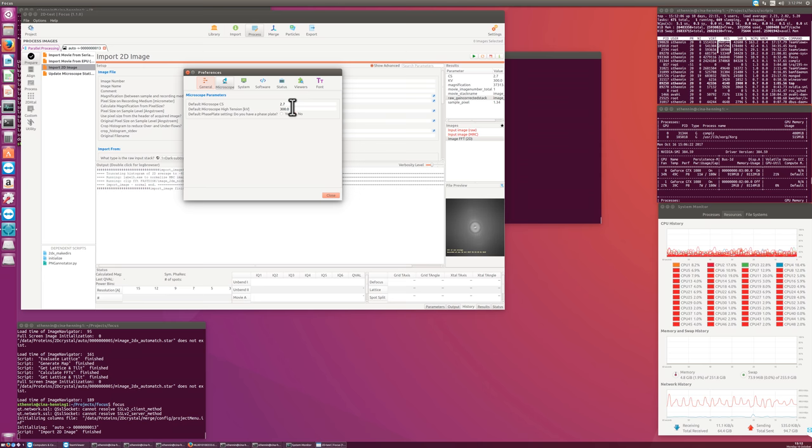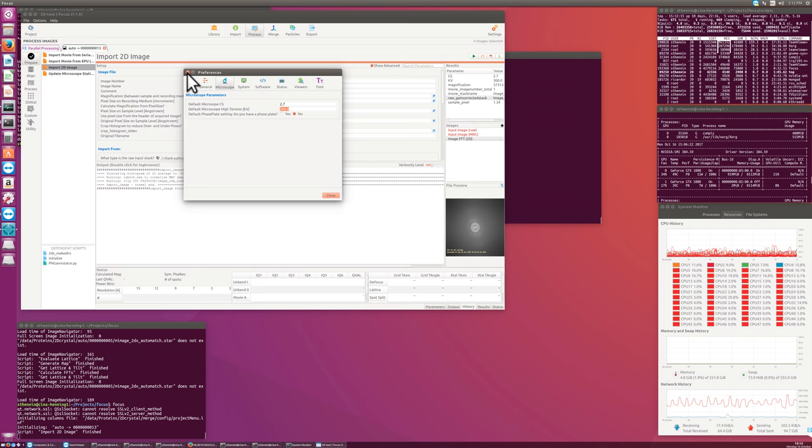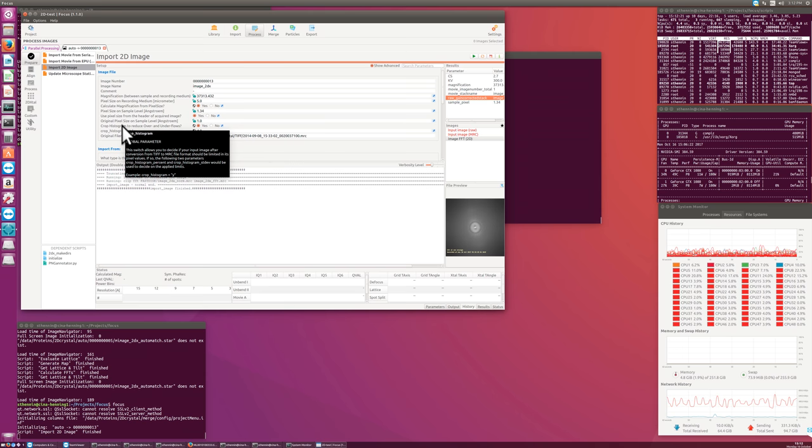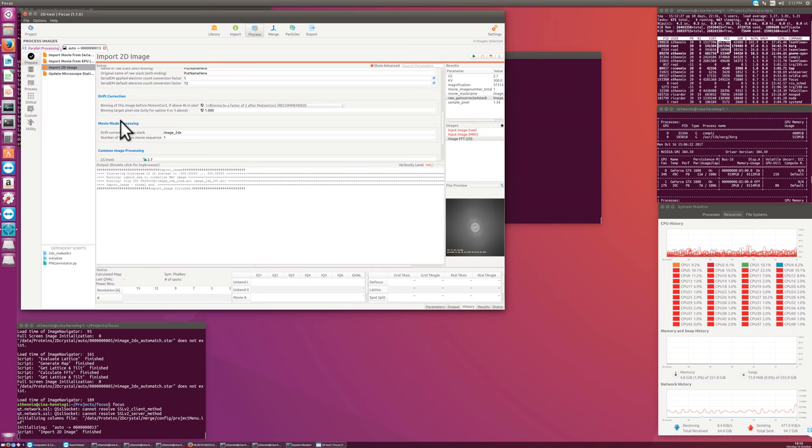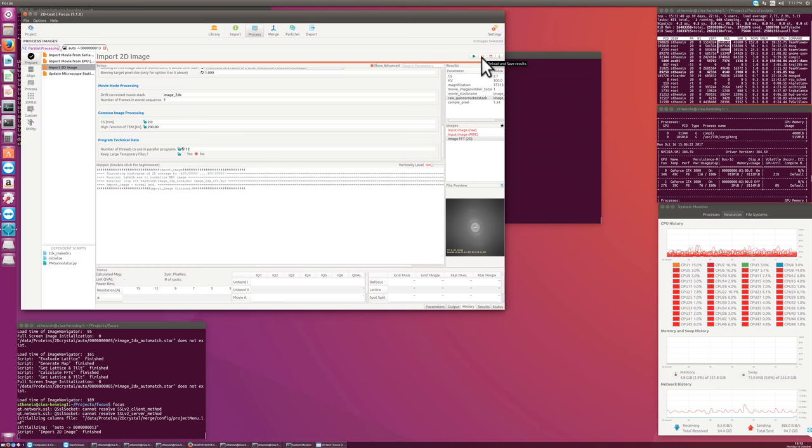There are some parameters here for CS and kilovolt and magnification. And they were set from default values. Some of the default values are accessible here in the settings tab. For example, the microscope default values and kilovolts are here. If there's nothing known about these images, then it uses what is here as preferences set for the microscope you have. But if you have an old data set from lots of images that were recorded with a different machine, one could also go now and adjust this manually here. For example, if we say this was a 2.0 millimeter CS and a 200 kilovolt microscope, you could adjust it here.